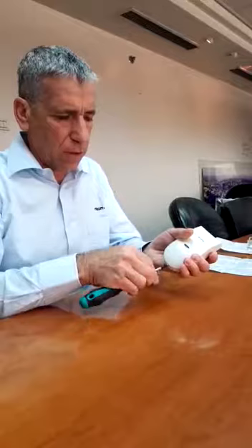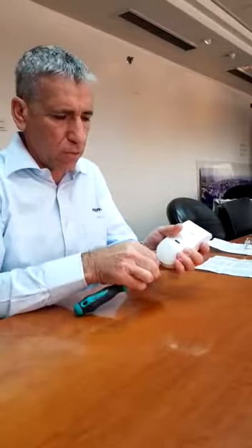I wanted to show you how to mount the passive infrared detector on the wall. The first thing you need is a Phillips screwdriver. You open the screw at the bottom of the sensor, holding down the cover, as it has a small spring that pops it open. You don't need to remove the screw — the screw stays connected.